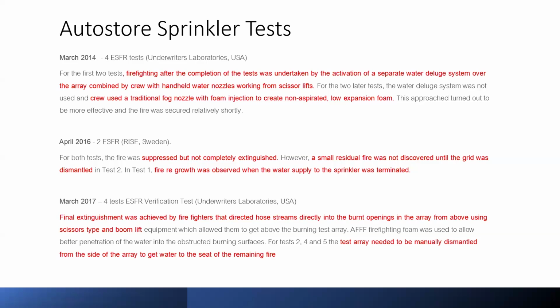Or now we are starting to create access for them. So we're still going to send people in. We're still going down this manual route, and we're still happy to expect the fire service to put these things out for us. So we're going down the suppress, contain, and then manual extinguishment route. So that was Underwriters Laboratories in the States, then more tests at RISE in Sweden, suppressed but not completely extinguished. Fair enough, it's a suppression system. Small residual fire was not discovered until the grid was dismantled. Fire regrowth was observed when the water supply to the sprinkler was terminated.